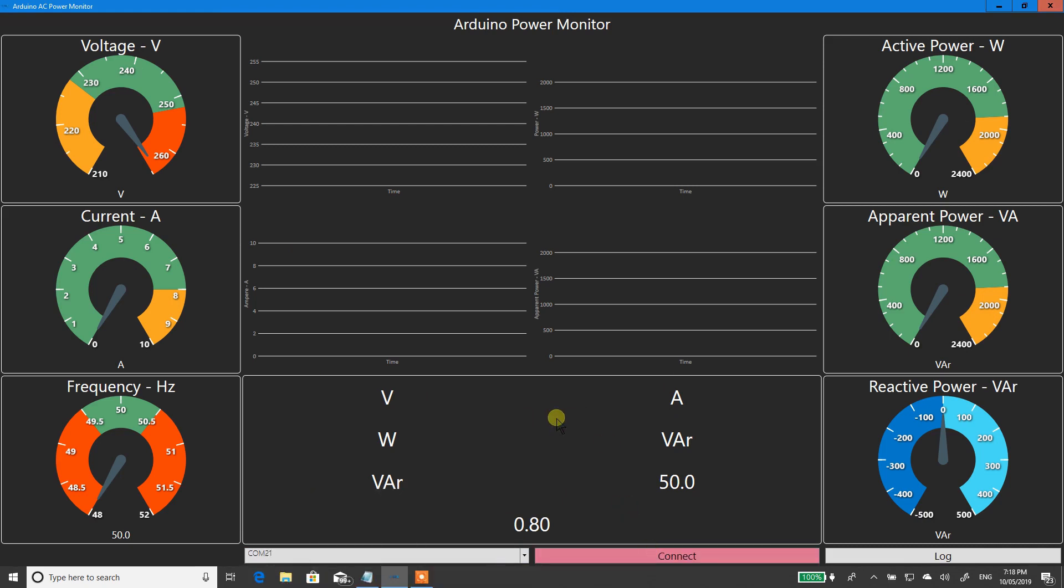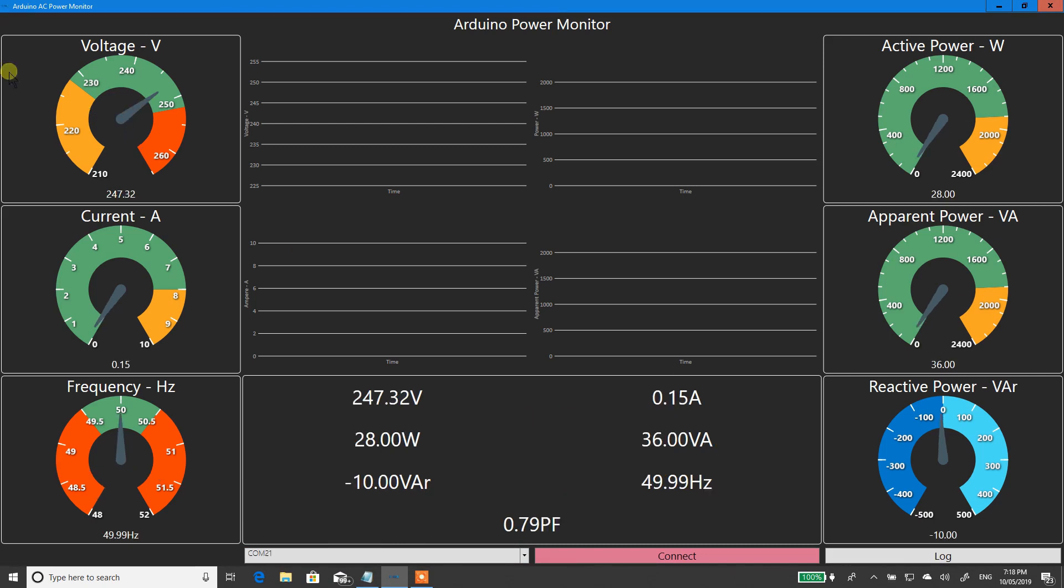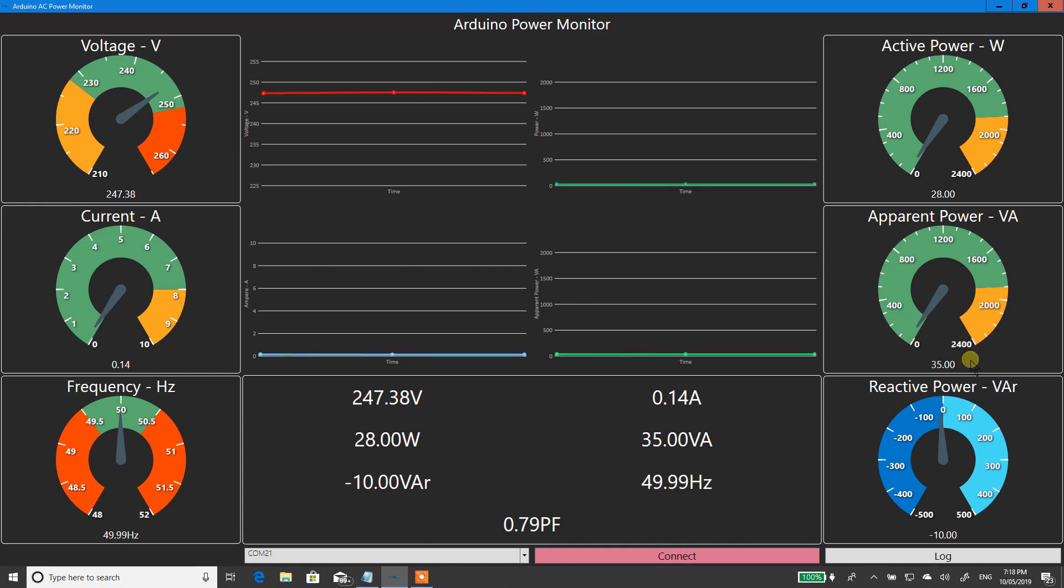You can select the COM port of your power monitor and hit connect. What it's going to do is connect to it and ask for the first quantity. So it goes and updates it. I've got 247 volts, 28 watts, 0.14 amps, 36 VA, 49.99 hertz, and negative 10 VAR. Now that's all up on the bottom as well.